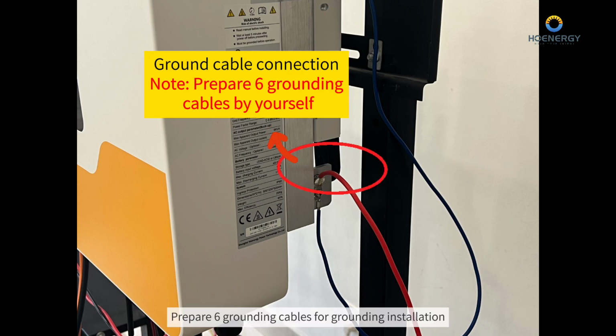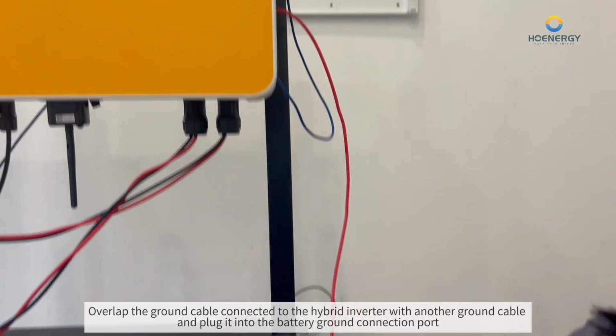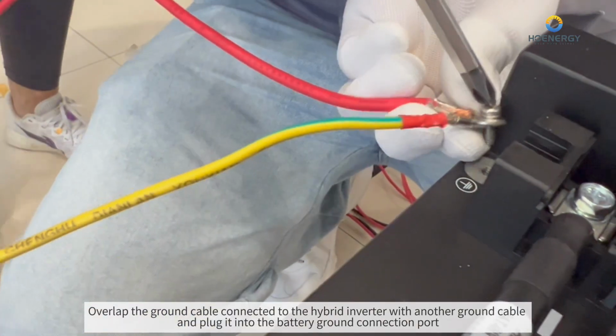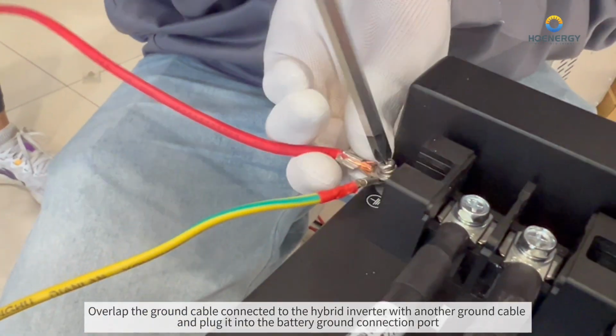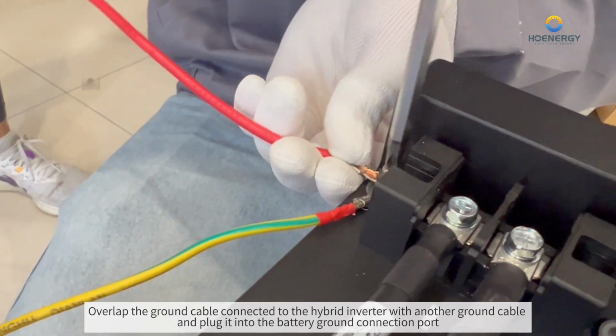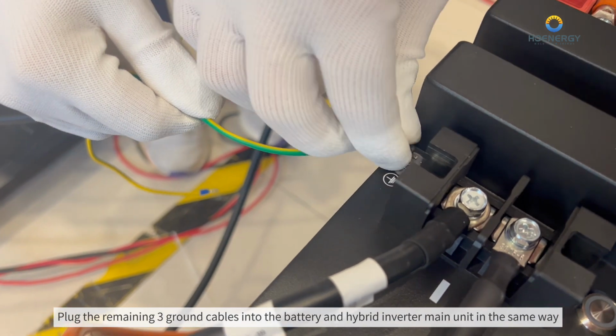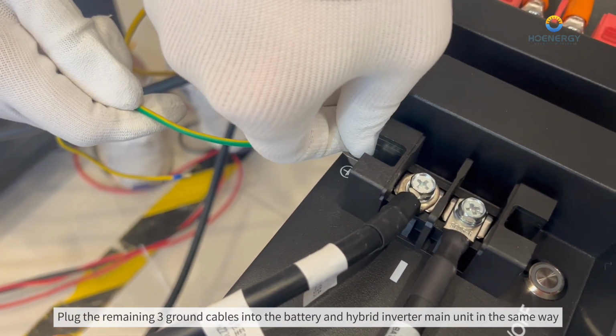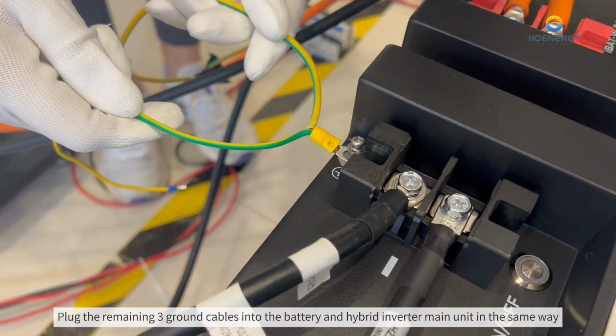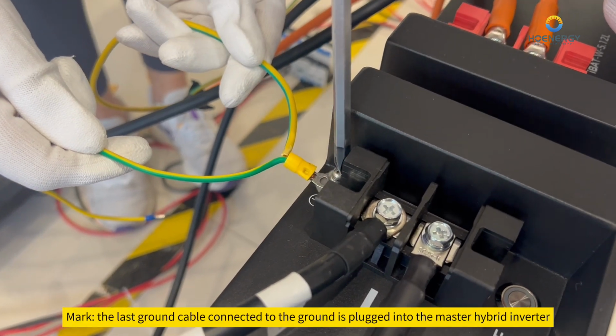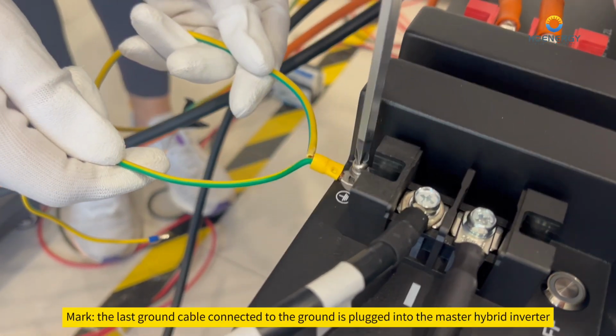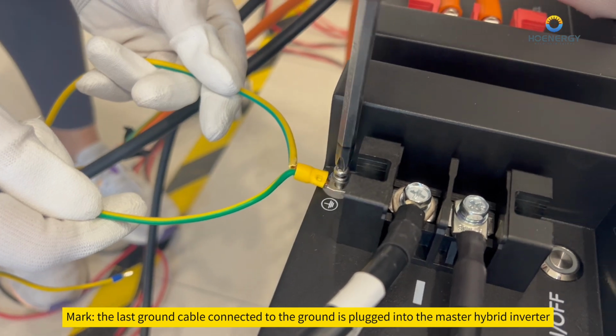Prepare 6 grounding cables for grounding installation. Overlap the ground cable connected to the hybrid inverter with another ground cable and plug it into the battery ground connection port. Plug the remaining 3 grounding cables into the battery and hybrid inverter main unit in the same way. Mark the last ground cable connected to the ground, and plug it into the master hybrid inverter.